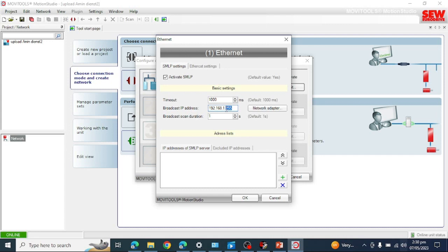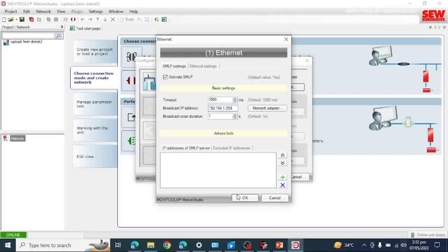This is the node field. If you want to search for a particular device, you must put that particular address here. For example, if I want to search node 192, I will put 192 here and it will only search that address. If you don't know which address you want, or if you are taking backup of all devices on this subnet, you must put 255 here, which means it will search all nodes from 0 to 255.